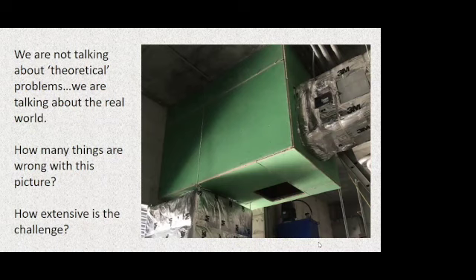So that strap support means one end of this plenum box is going to fall away from the wall as soon as it's exposed to fire, very, very, very shortly after. In no way, shape, or form is that going to get close to 2 hours. We also realize that the technical manuals for every product in this class do not allow the bearer to go underneath the insulation. So we see that happening on the plenum box as well as the duct. If it wasn't off screen, we'd see the bearer was also wrapped.